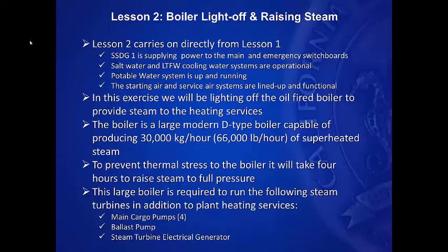You should see no steam pressure rise at all within the first hour, so we don't expect to see any pressure rise during this scenario. If you were to see steam development in the boiler drum, you would need to immediately shut the fires out until an hour has elapsed from the start of the warming up process.